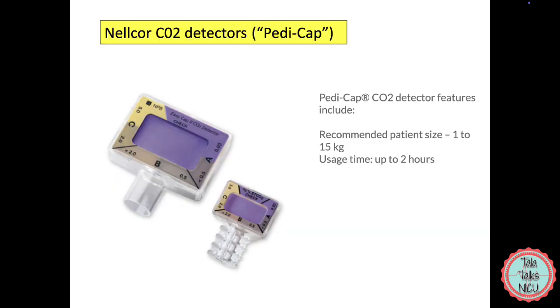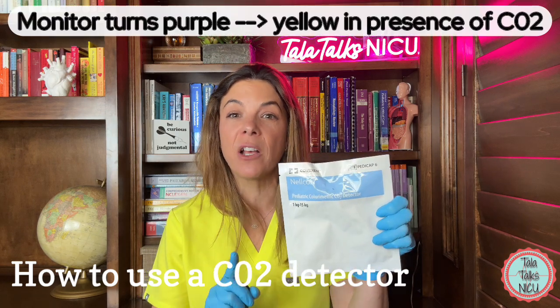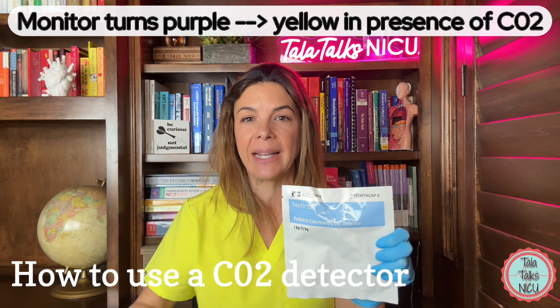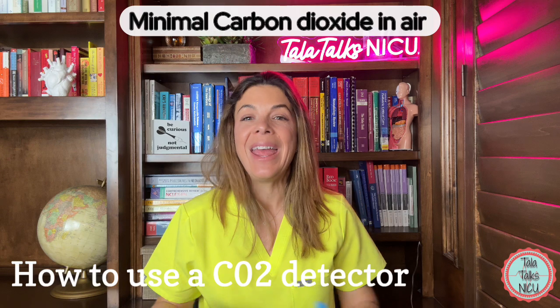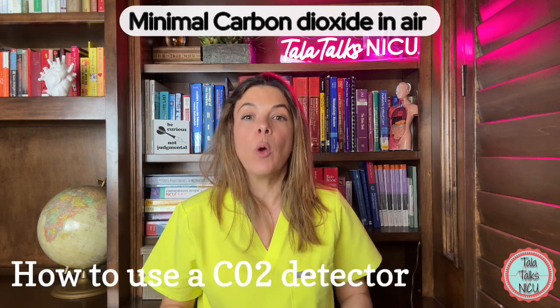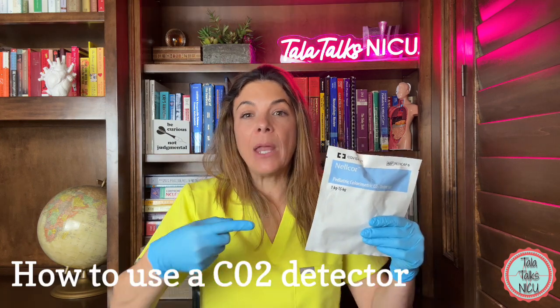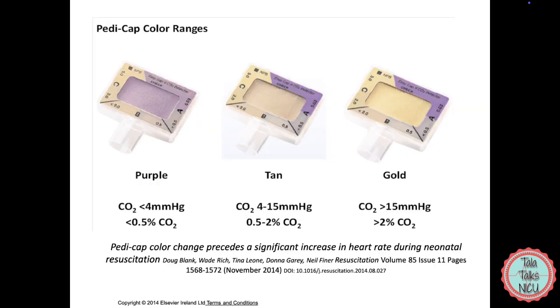Pedi-Cap is a trade name, by the way. There are lots of different manufacturers that make different types of monitors. The vast majority of them turn from purple to yellow when they are detecting CO2. Remember that the amount of carbon dioxide in air is super low — less than 0.03% — so normally a lot of these detectors are a purple color, and then when they're exposed to carbon dioxide, it will become a more yellow color.